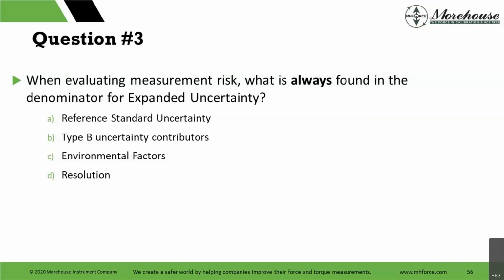Yeah, so the correct answer is A. The reference standard uncertainty is always found in the denominator. Resolution, P14 talks about if we have that bit of standard deviation from repeatability, that maybe we don't need to put it in. ANSI Z540.3 says we always need to put it in. Type B contributors, more than likely they may find their way in or not. So we're always going to see that reference uncertainty. That's the one thing you're never going to avoid, right?